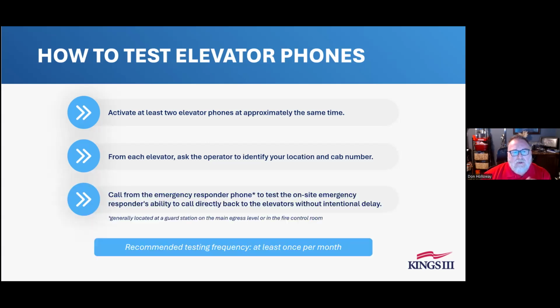Call from the emergency responder phone tests the on-site emergency responder's ability to call directly back to the elevators without intentional delay. It's generally located in the guard station, main egress levels, or fire control. These are called lobby phones in the code, also referred to as master stations. They're usually located in a FACP room or fire command center. Once you go in there, it should be able to connect to the actual phone inside the elevator without delay, becoming priority, so emergency personnel can actually communicate with the people inside the cab when they need that.